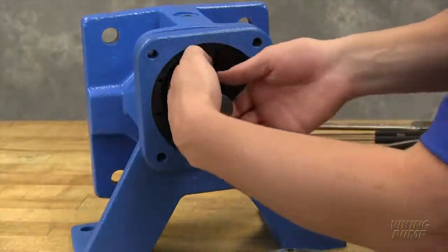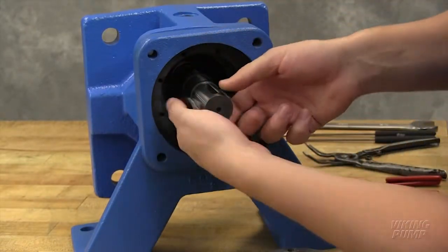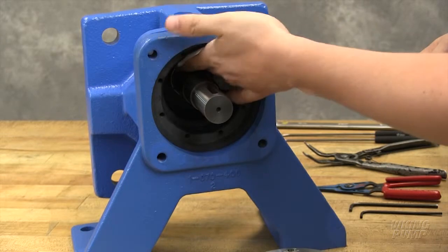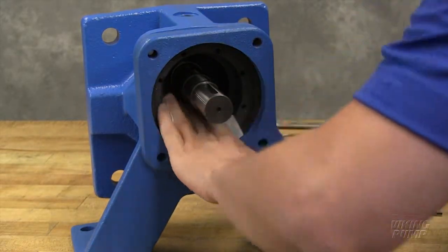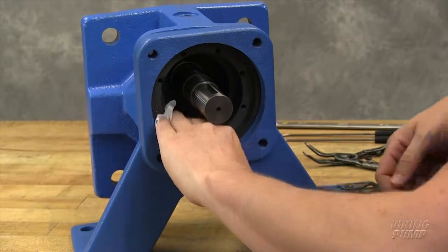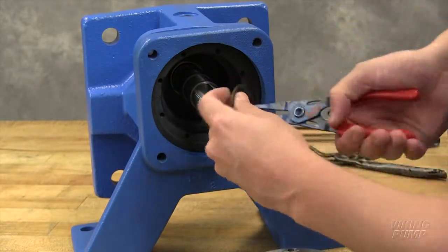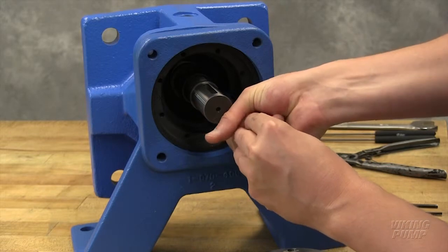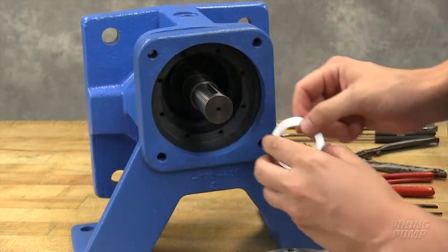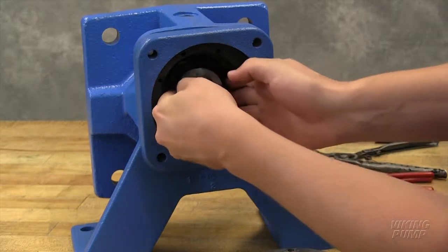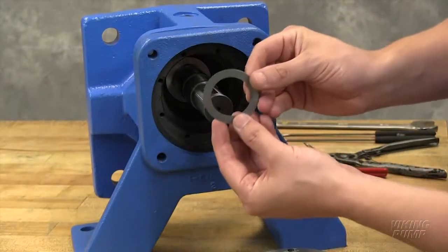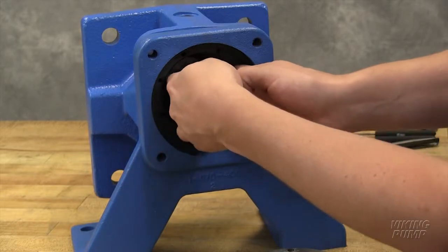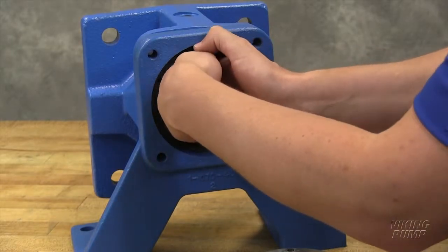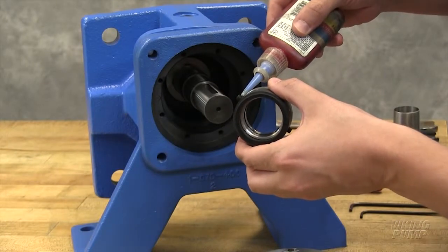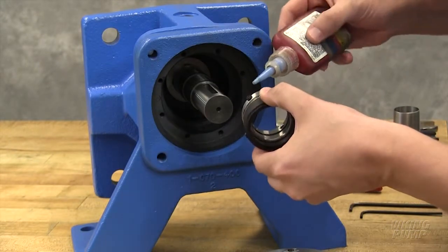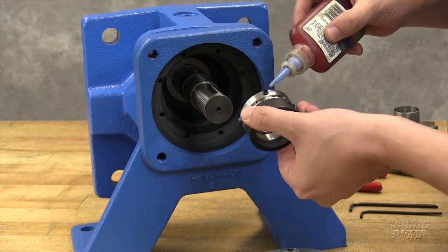Use a lint-free towel to clean the shaft and the seal chamber inside the pump. Make sure both are free of dirt or grit. Also clean the counter bore where the seal holder O-ring is located. Install the retaining ring into the groove in the drive shaft. Install the seal washer against the retaining ring and install the seal shim against the seal washer. Be careful not to scratch the shaft in the sealing area. Loosen the set screws on the seal and apply a dot of Loctite 242 to the set screw threads.